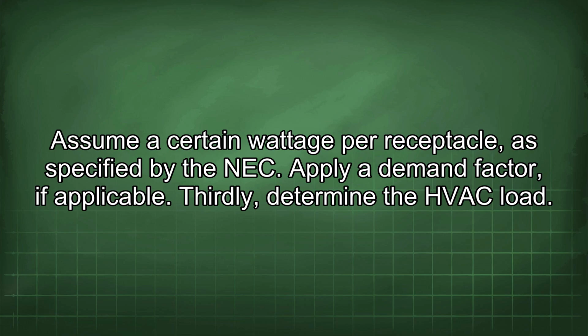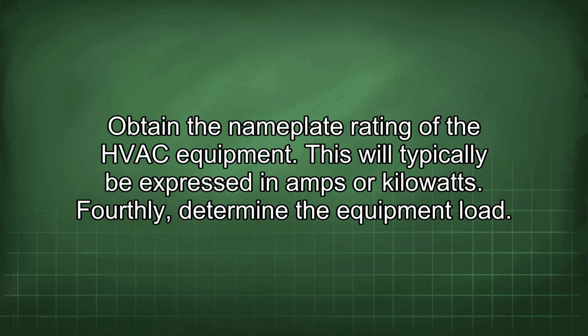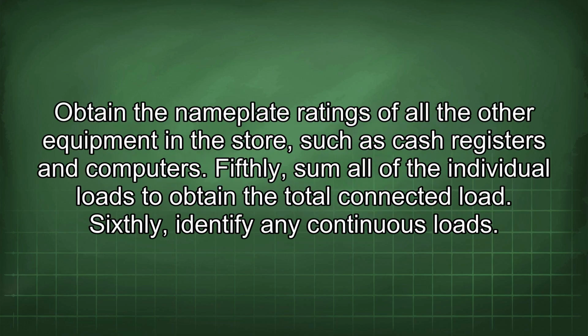Thirdly, determine the HVAC load. Obtain the nameplate rating of the HVAC equipment. This will typically be expressed in amps or kilowatts. Fourthly, determine the equipment load. Obtain the nameplate ratings of all the other equipment in the store, such as cash registers and computers. Fifthly, sum all of the individual loads to obtain the total connected load.